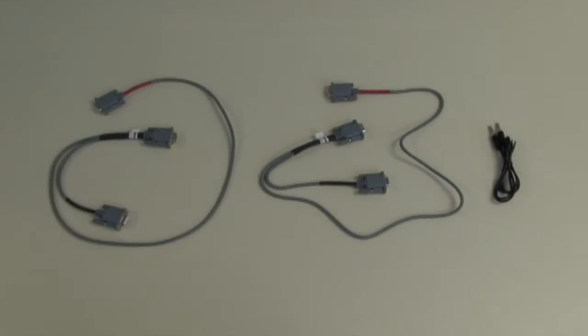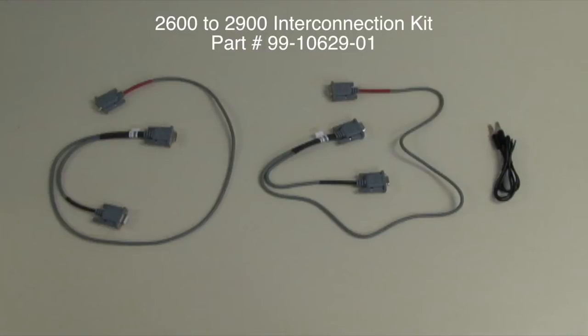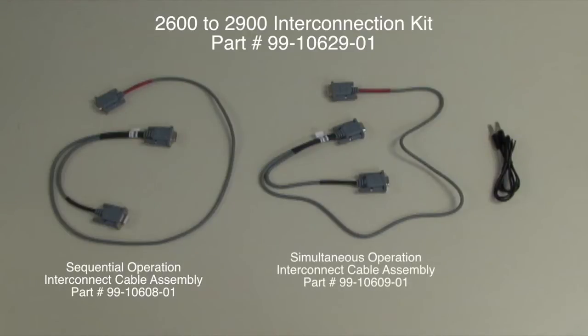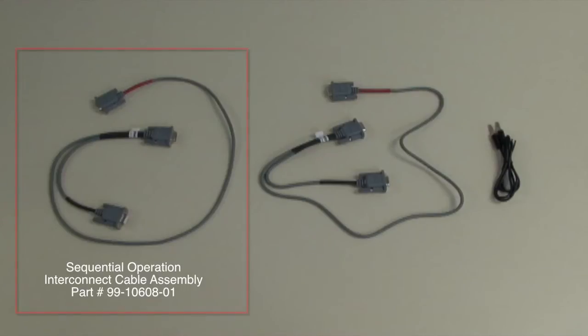To interconnect these two units, you will need the 2600 to 2900 interconnection kit. This kit contains the following parts: sequential operation interconnect cable assembly, simultaneous operation interconnect cable assembly, return interconnection cable. It is important to note that you will use either the sequential operation or simultaneous operation cable interconnections, not both. The sequential operation cable set will cause the Hipot test to run after the ground bond test has completed. The simultaneous operation cable set will cause the ground bond and Hipot test to run at the same time. For this video demonstration, we will be using the sequential operation cable set.